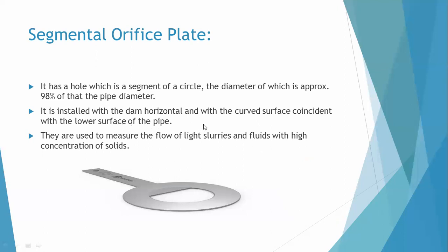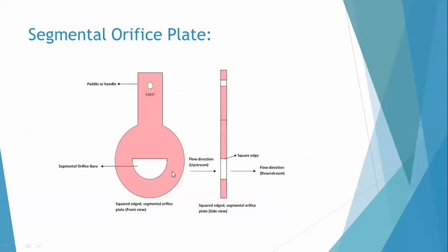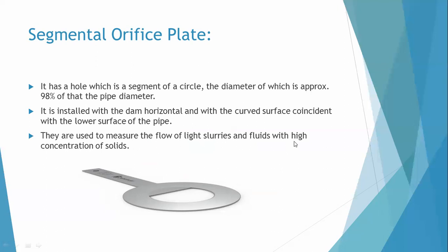The segmental orifice plate is installed with the dam horizontal and with the curved surface coincident with the lower surface of the pipe. The curved part of the hole aligns with the lower surface of the pipe. Segmental orifice plates are used to measure the flow of light slurries and fluids with high concentration of solids.